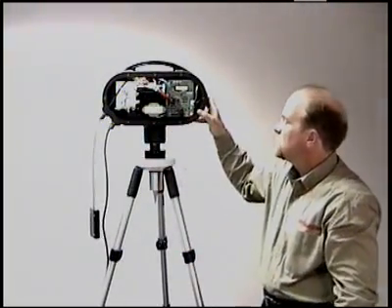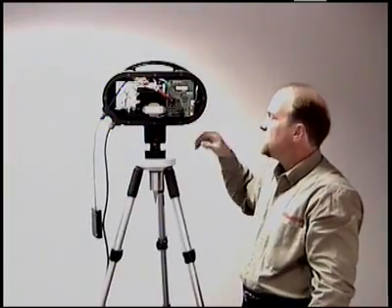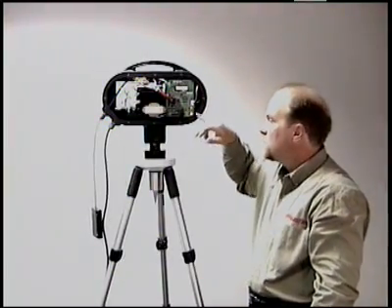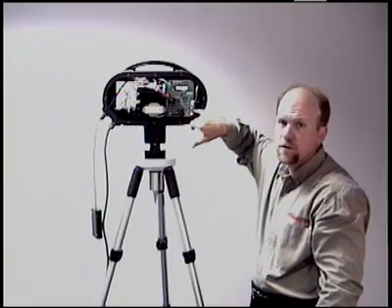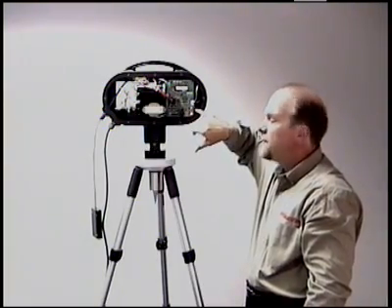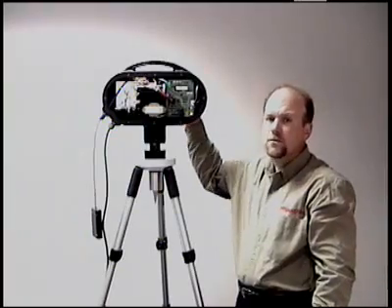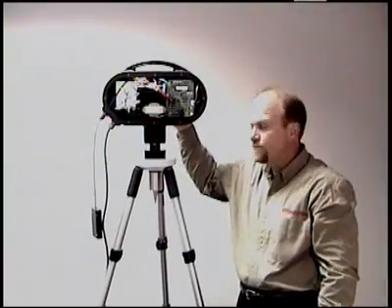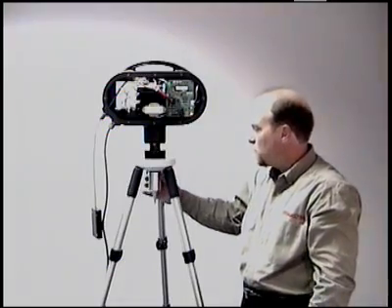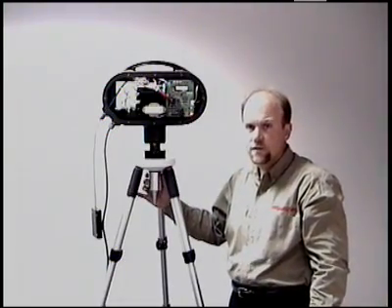What we are actually doing is measuring the amount of cable released with an optical encoder and a pulse wheel, which pulses at about 80 times per foot. This pulse wheel is directly connected to a timing pulley on the mechanical side of the unit.